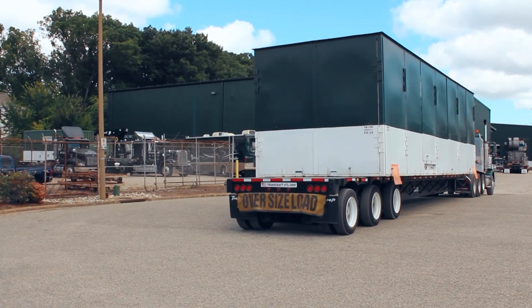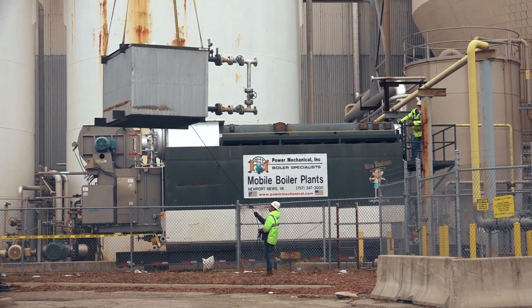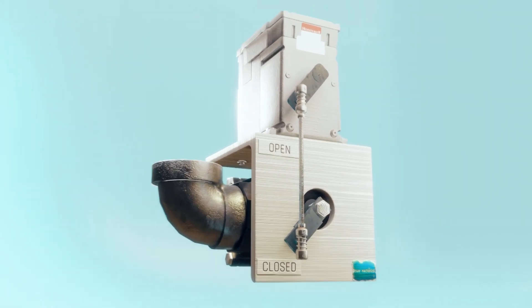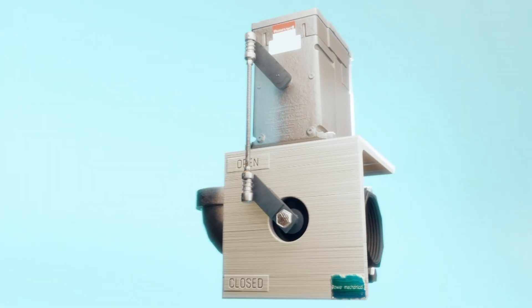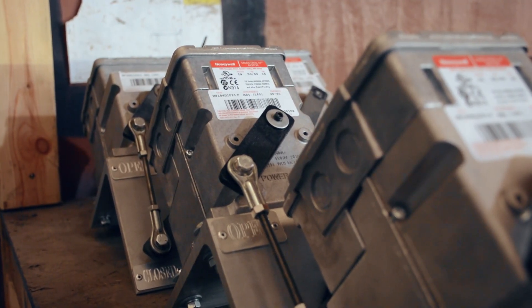For years here at Power Mechanical we used these gate style valves in our rental fleet on many of our larger capacity boilers and still see this design on some applications. Over the years we found that one of the worst calls you can receive from a customer is one that is feed water related, and that led us to designing our own feed water valve that can deliver the same efficient and reliable feed rates. We're going to head over to Powerhouse Valve to speak with Matt about some of the design features of this Honeywell modulating feed water valve that we designed.